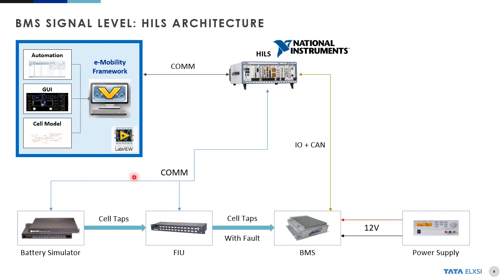The cell taps then go through the fault insertion unit or FIU, which is again connected to NI HILS. The fault insertion unit allows you to create individual faults on cell tap lines, for example open circuit, and see how the battery management system responds to that.